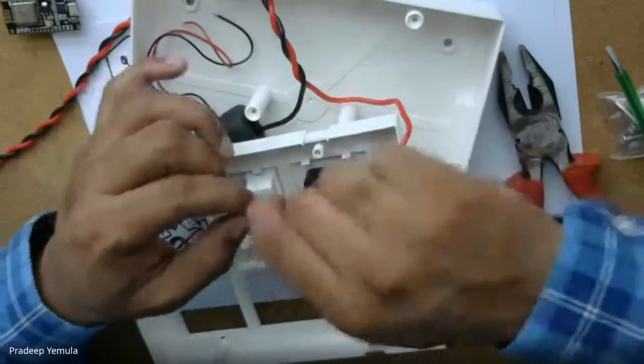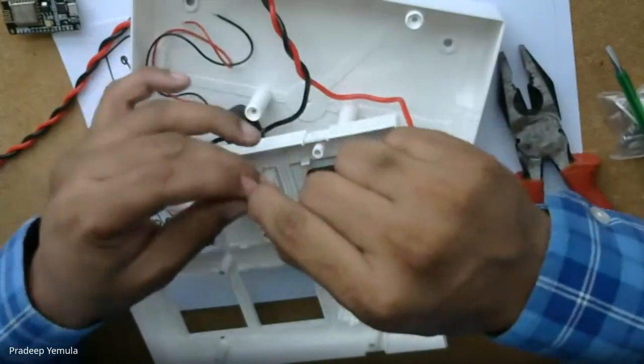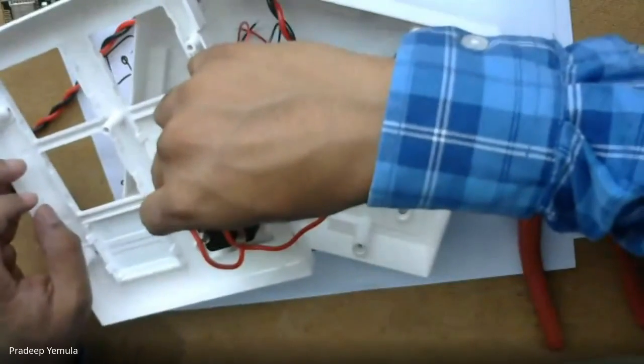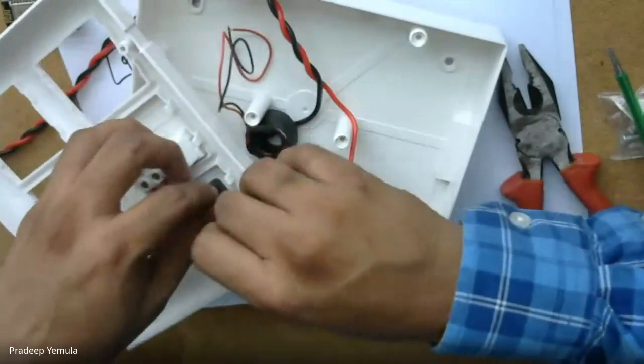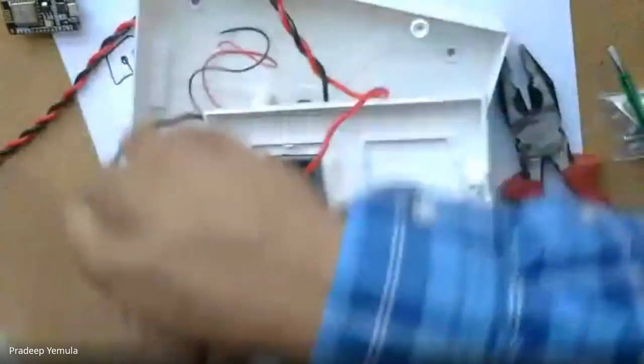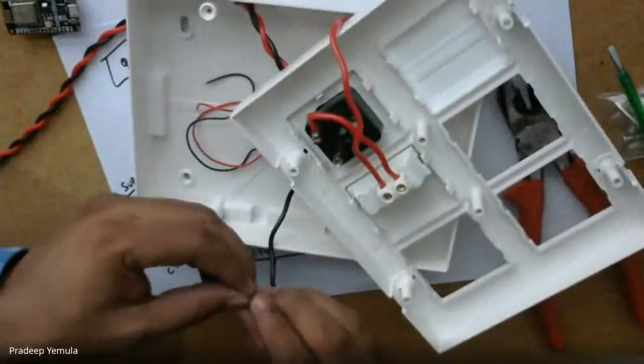Sir, is there a specific reason that we are taking the CT through neutral? We can take it through the line also, because full load current is going through the line. Anyway, neutral and line both carry the same current, so it's not about the current. The reason is we found that in the circuit diagram given for the particular component, they have connected it in the neutral. So just to be consistent with that, you are doing it. But your question is right, we can connect it in any way.